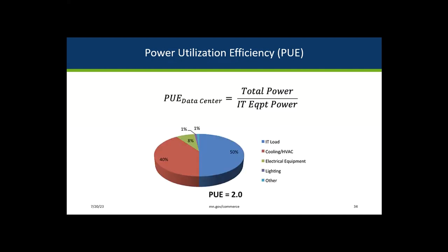As an example, in the pie chart shown, almost 50% of the power drawn by this data center is from infrastructure loads like cooling, HVAC, and lighting. Since 50% of the power is IT load, the PUE of this data center is 2.0. Typically, the PUE of a data center is between 1.25 and 3.